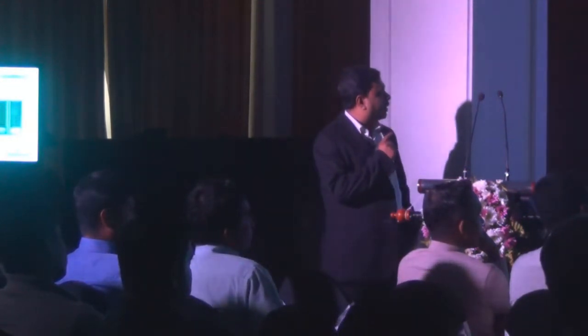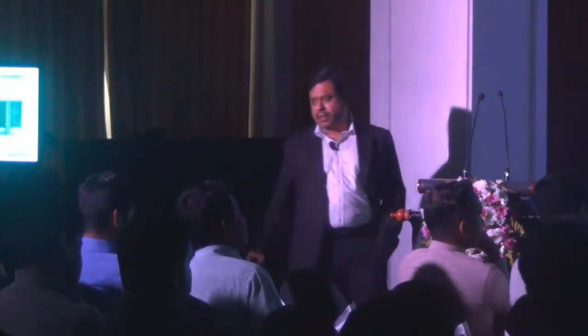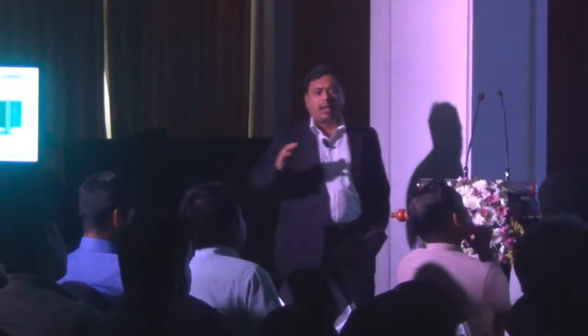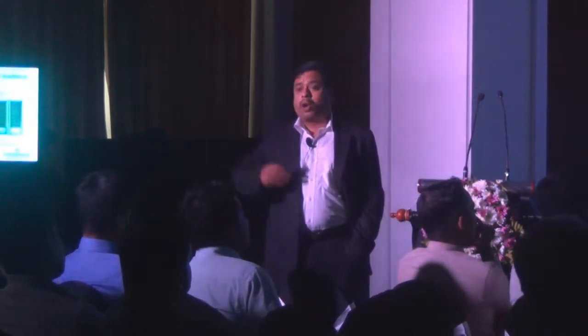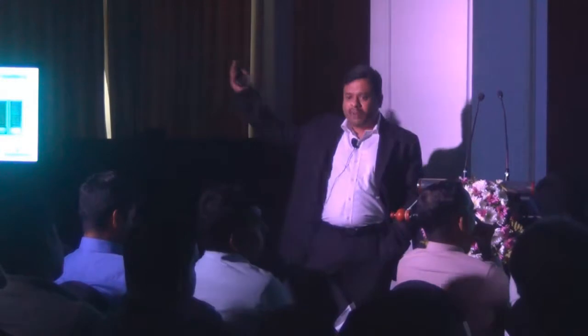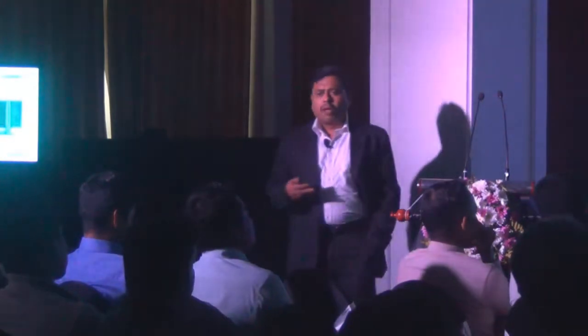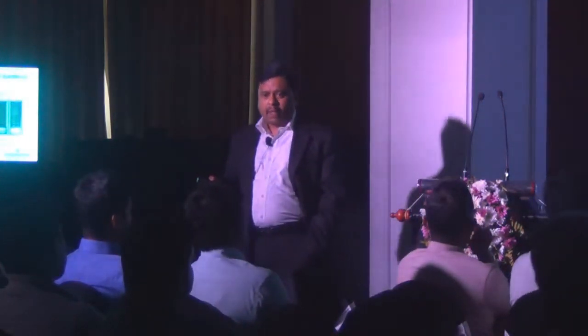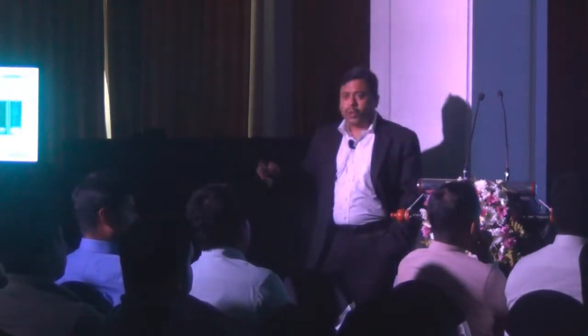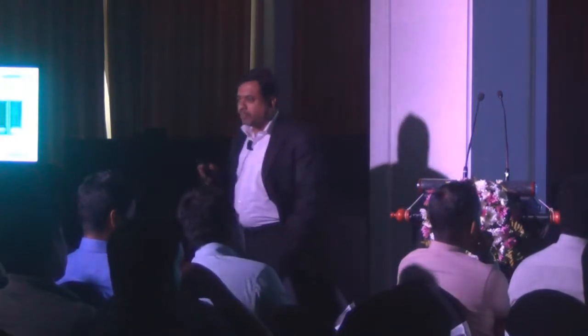If you see here, the first UPS system has only one module of 30 kVA, 30 kilowatt, with inbuilt batteries available. See, when a customer normally buys a UPS system, he always thinks in mind, what will be my future requirement. He may not be aware of how fast or how much he will reach towards that. But this gives you a fantastic solution for those customers where pay as you grow is the strategy. If your loads get increased on a periodical basis, you can keep increasing your capacity by adding modules at any given point of time.